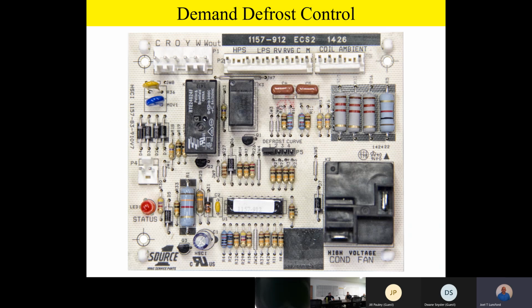It'll then stay in defrost until that switch on the outdoor coil comes up to about 55 to 60 degrees Fahrenheit, and then it'll open electrically, and once it does, it terminates the defrost and resets the timer. So the big difference between a time temperature and a demand defrost control is the time temperature control just has a simple little Klixon switch, click, click, click, mounted on the coil outside to monitor the temperature of the coil. It does not have an ambient sensor.